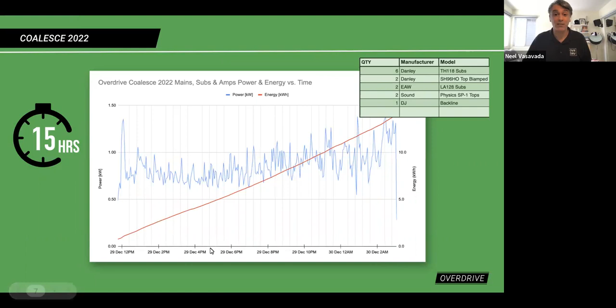But the way batteries work is very different than generators, because we can store the energy, it's only the average that matters. It turns out the averages can be fairly low because there are peaks and valleys. So in this situation, we were able to run 15 hours completely sustainable on electricity alone. Now, from a generator point of view, you wouldn't think this is possible because a generator has to be sized for that peak load, which here was 1.38 kilowatts. But since the batteries charge to a more reasonable average load, we can now run events for long periods of time on stored battery electricity.